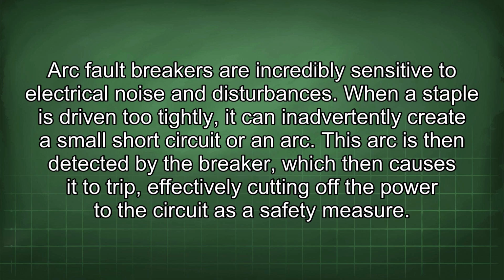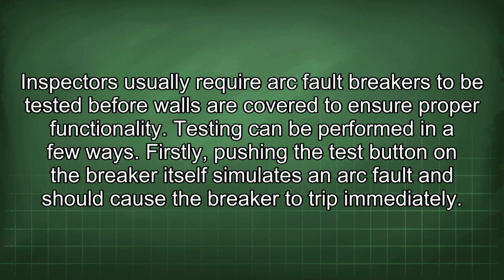When a staple is driven too tightly, it can inadvertently create a small short circuit or an arc. This arc is then detected by the breaker, which then causes it to trip, effectively cutting off the power to the circuit as a safety measure. Inspectors usually require arc fault breakers to be tested before walls are covered to ensure proper functionality.